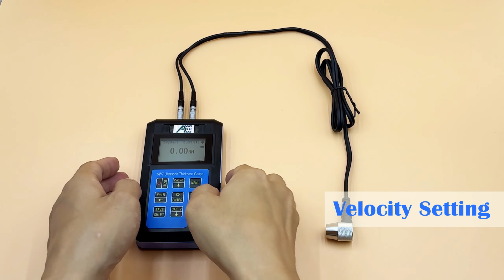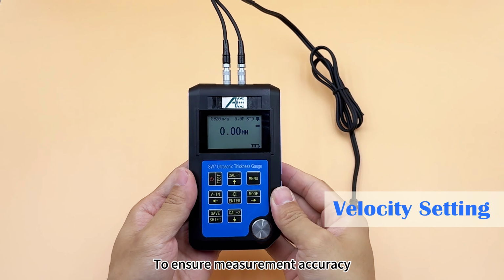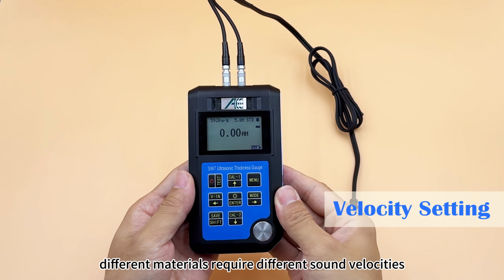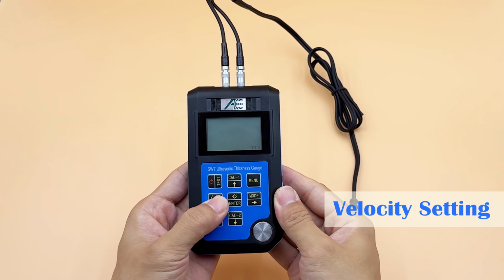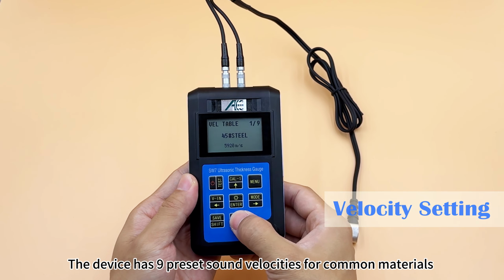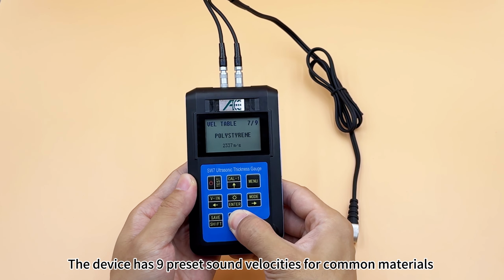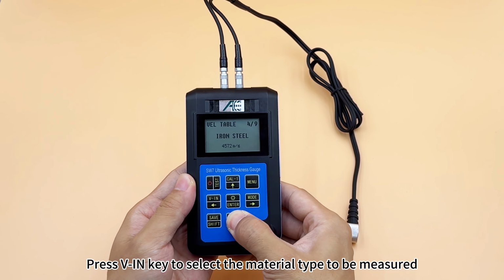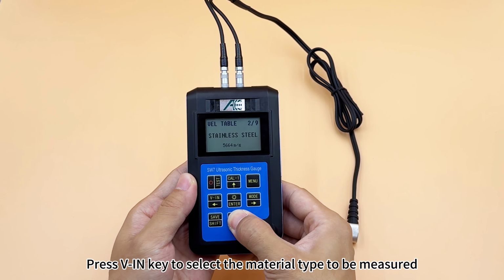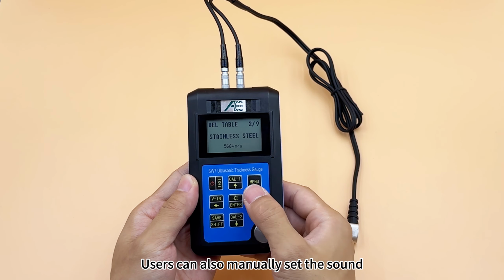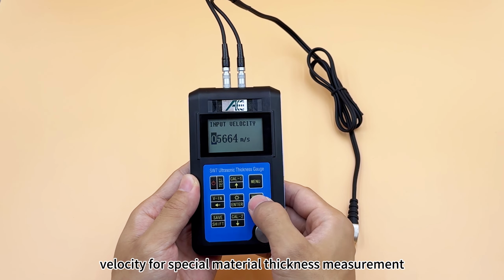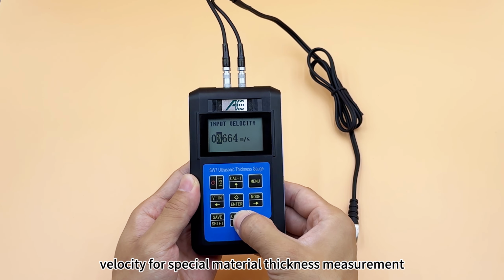Velocity setting. To ensure measurement accuracy, different materials require different sound velocities. The device has 9 preset sound velocities for common materials. Press V-IN key to select the material type to be measured. Users can also manually set the sound velocity for special material thickness measurement.